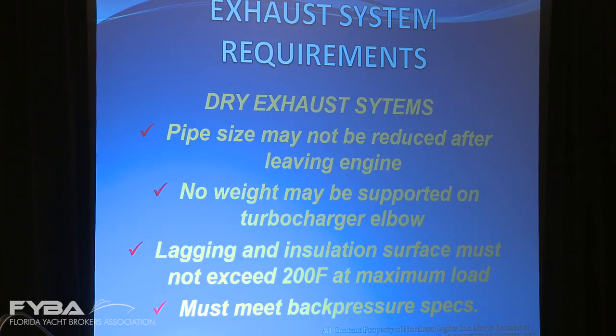So dry exhaust systems are a little less common in small generators, but fairly common in big generators, and we do build a lot of big generators. So with dry exhaust systems, again, we can't reduce the pipe size after it leaves the engine, but something a little trickier, we can't support any weight on the turbocharger exhaust elbow. That weight has to be supported either by bracketing in the exhaust system or from overhead with a flexible connection.